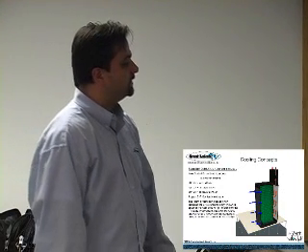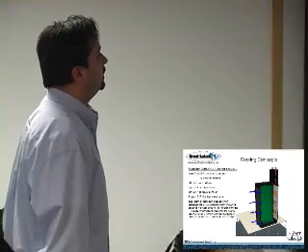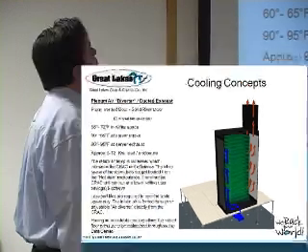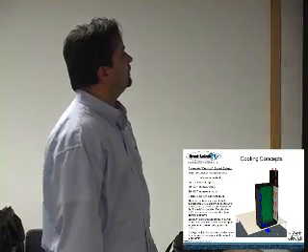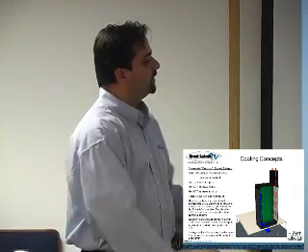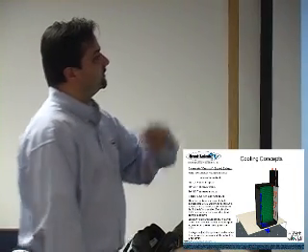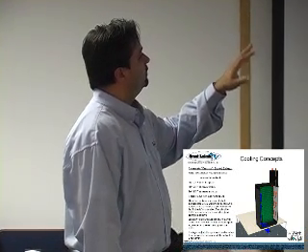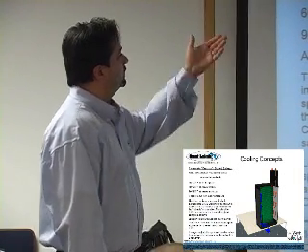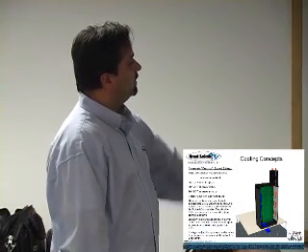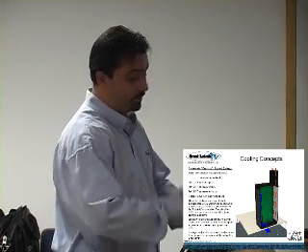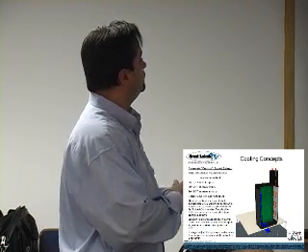So we're seeing this one, and the next slide is the next trend. This one is what we're going to call just a plenum: raised floor ducted to the front of the enclosure, and a ducted exhaust. So you still have a vented front door and a solid rear door, and still with a fan assist if you want. All with the redundant intake, redundant power.